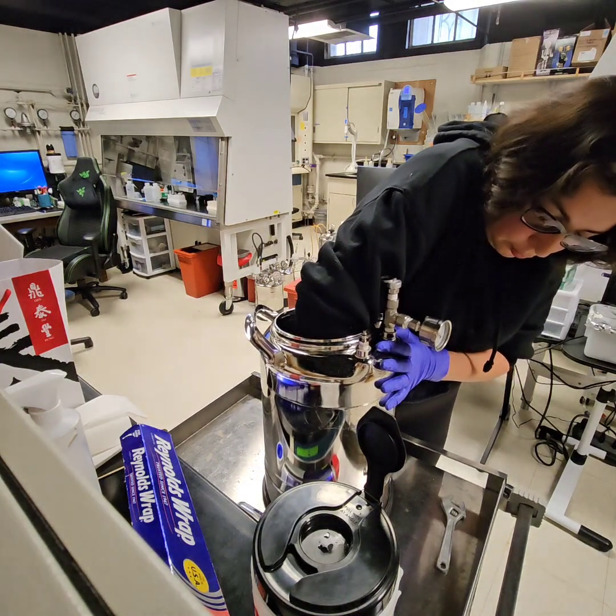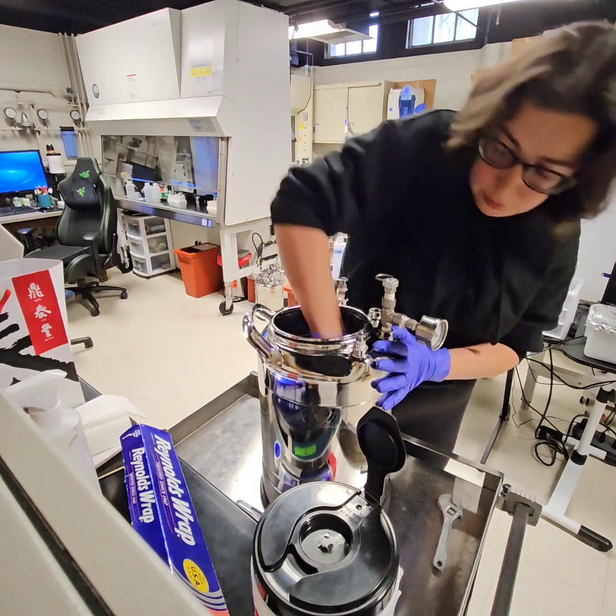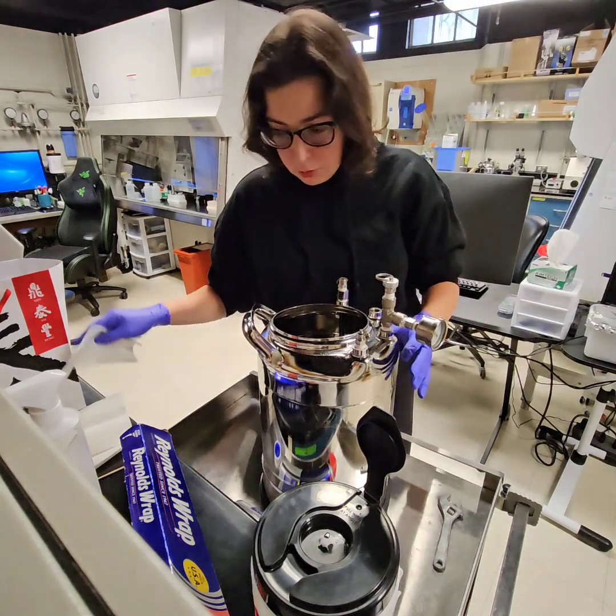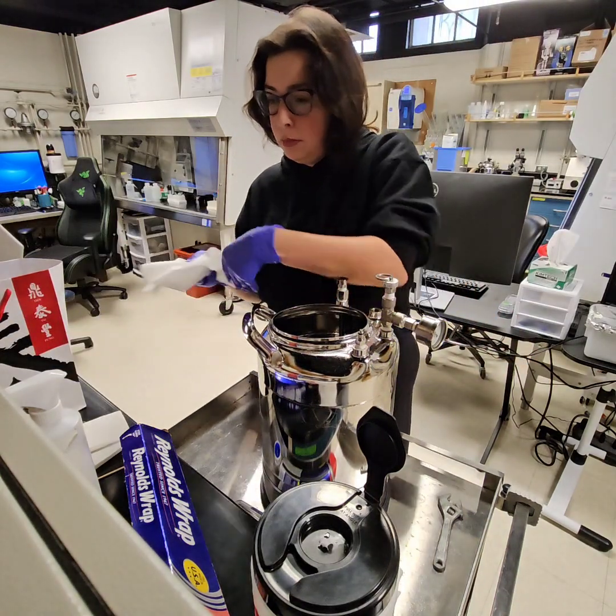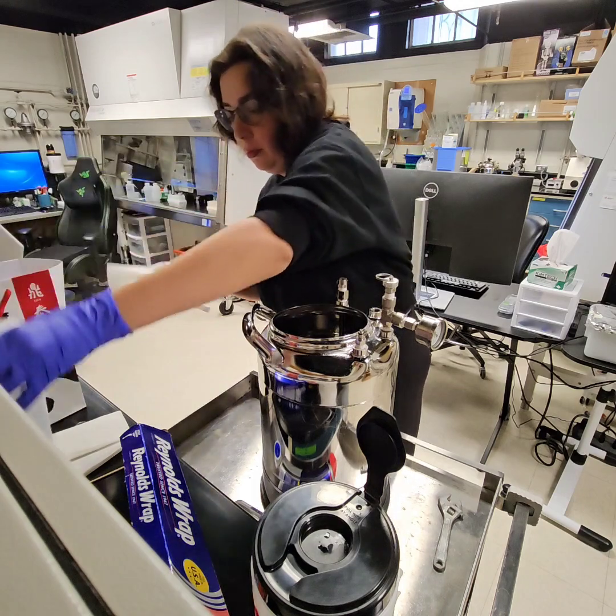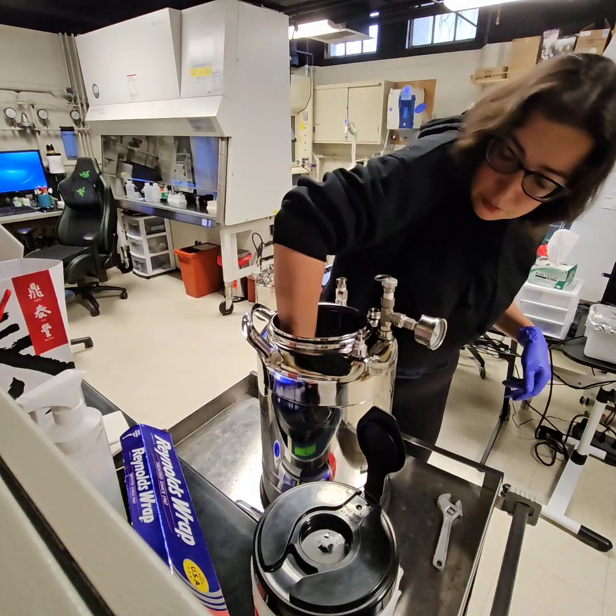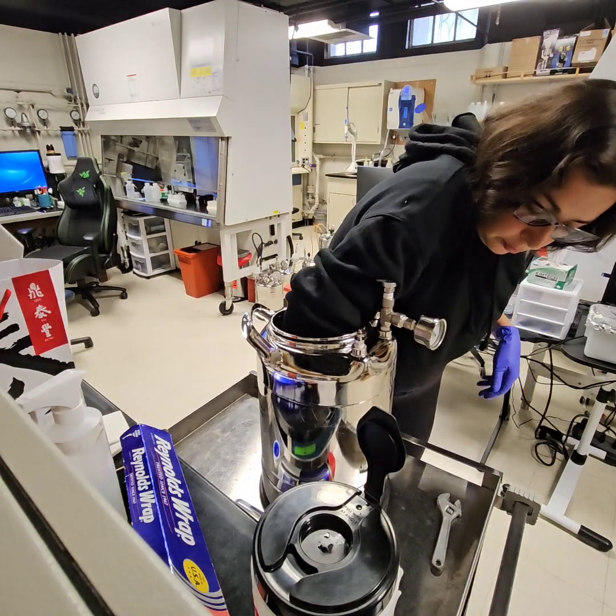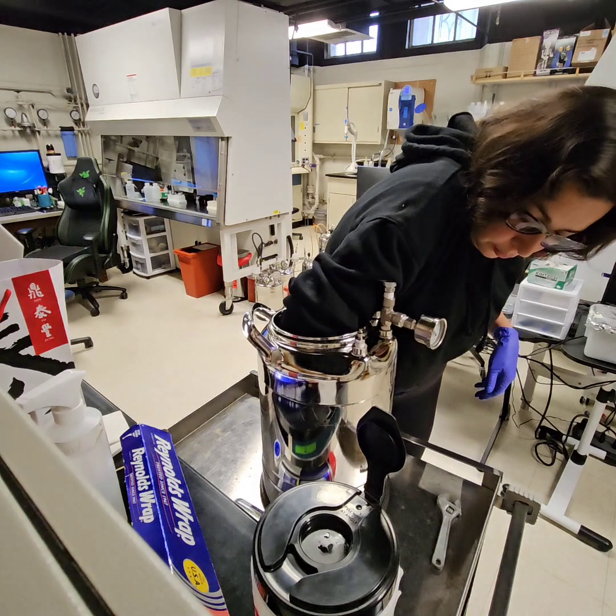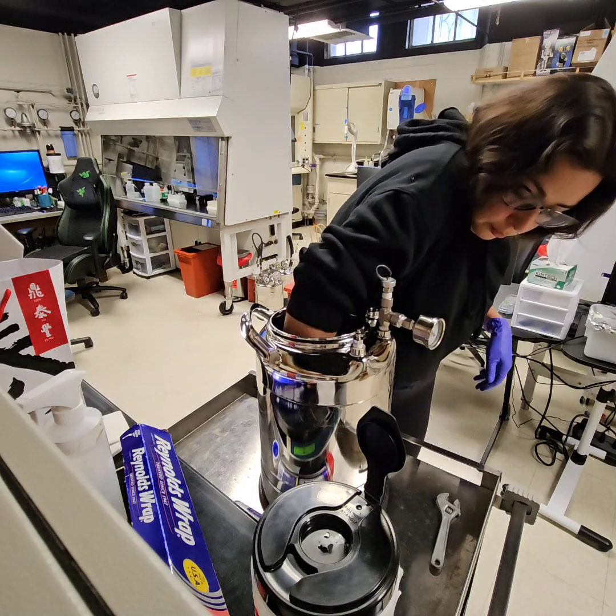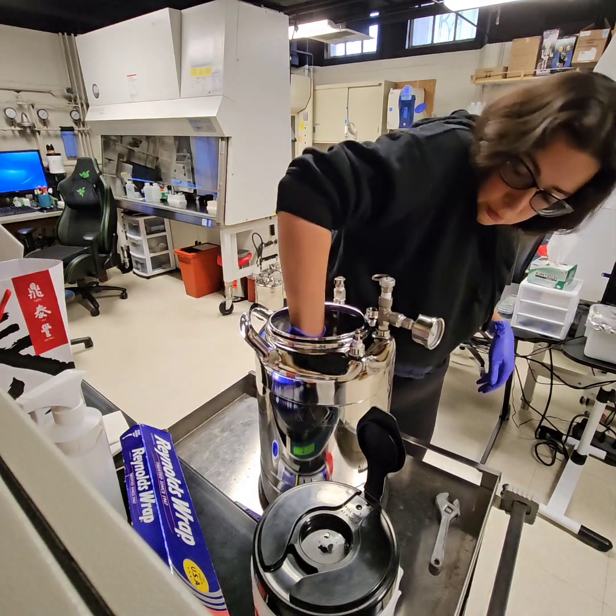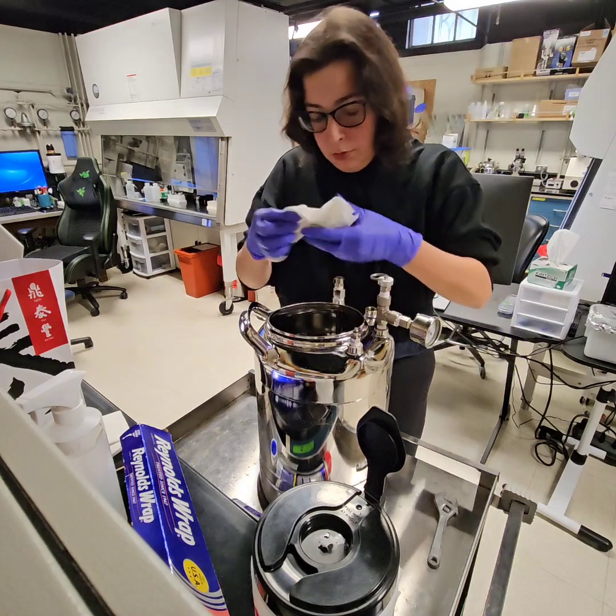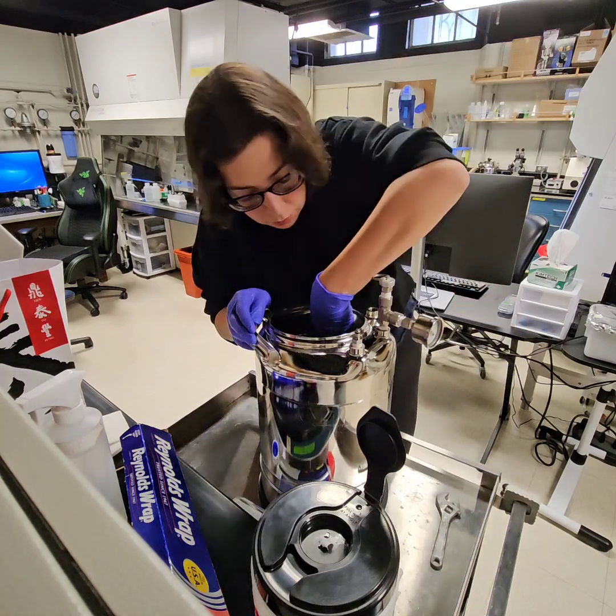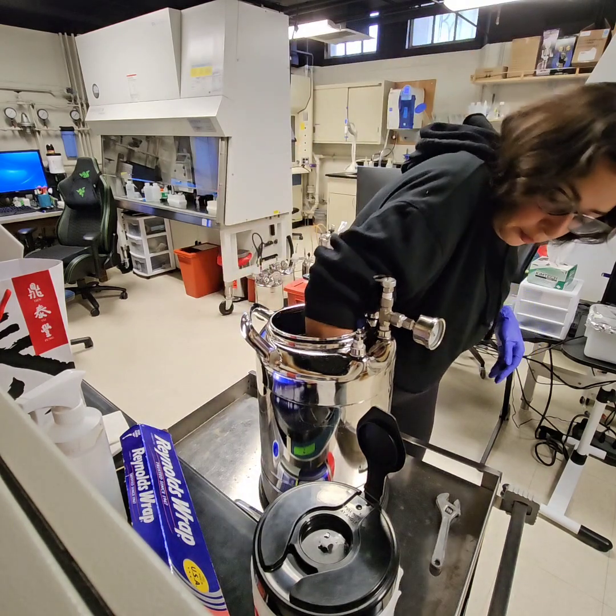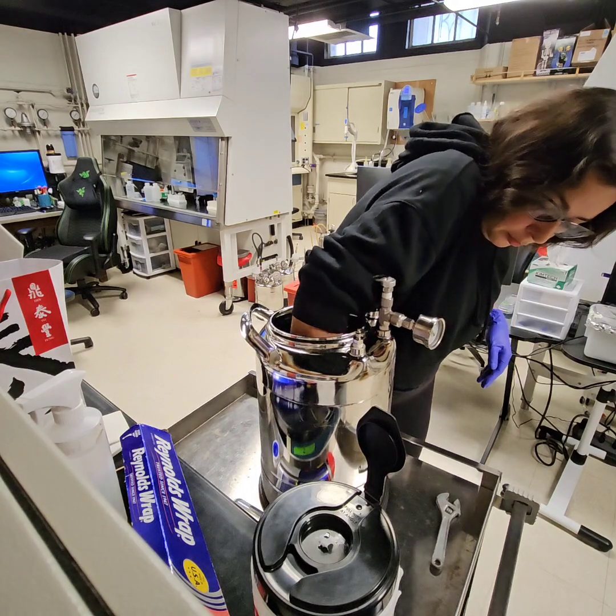lighter duty tasks. It really is very important to make sure that there's no residue of paper towel or any other debris at the bottom of the tank, because once we fill this up, if, for example, we're doing submicron work and we choose to run without a filter, we don't want any particles to go through any of the sheath lines. We want it to be completely clean when we pour the sheath in, so it's really critical to make sure there's nothing left behind.